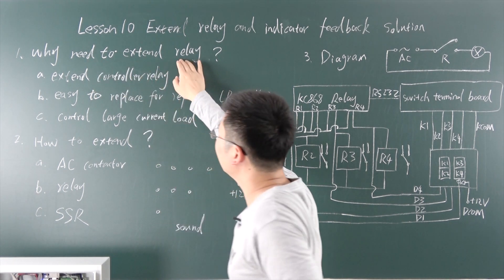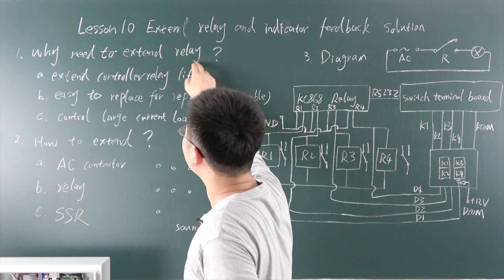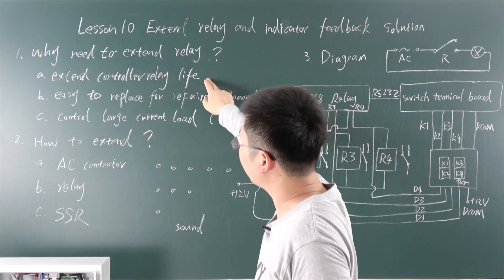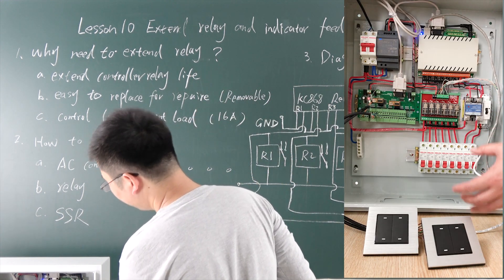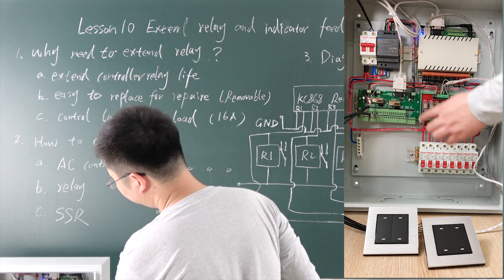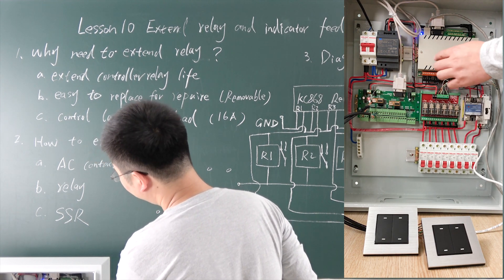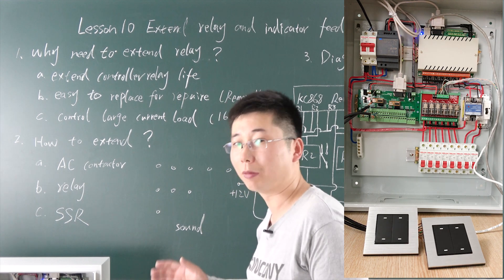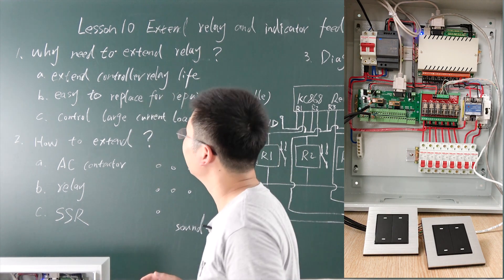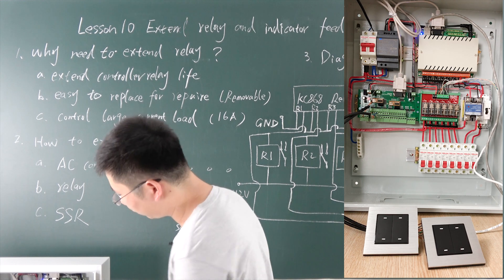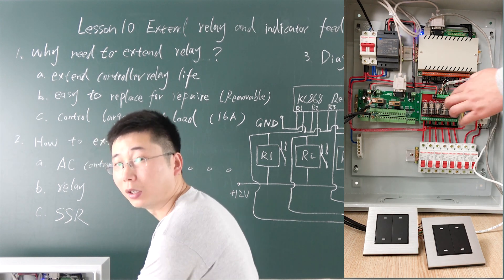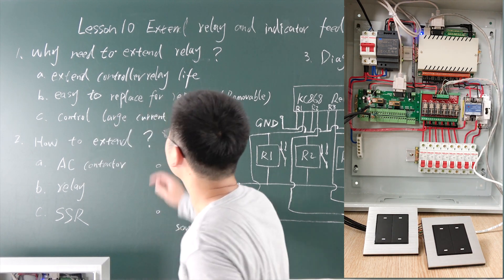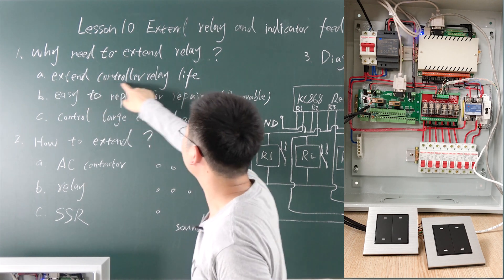Why extend the relay? Because extending the relay extends the controller relay life. Your power load — all the large current — goes through this external relay and not through the internal controller relay. So the relay inside the controller box carries only very small current. The large power pulse will impact the external relay, protecting the internal one.